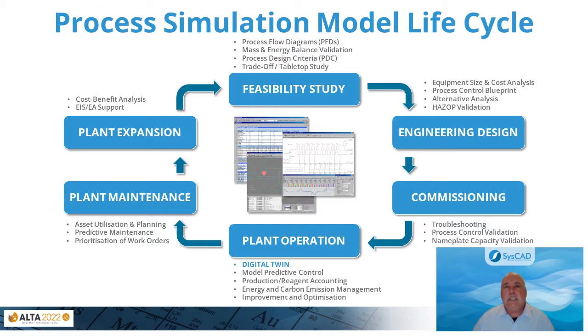A process simulation model follows typical stages of a process plant lifecycle. In feasibility, the model is relatively simple and can provide insight into mass energy balance and process design. As you progress, the model becomes more complex. Dynamics can be incorporated at later stages of the design, testing and commissioning for process control, equipment and pipe sizing, nameplate capacity validation, etc.